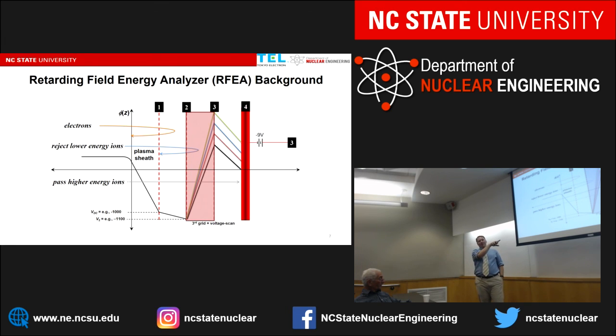The measurement across the resistor on the fourth grid is different, because across the resistor there's going to be a potential drop, so the high part of the potential goes into the high voltage line of the DMM, and the low potential goes into the low voltage line. And as I mentioned, that low voltage line can only sit up to 500 volts above computer ground. So if I scan, taking into account what the VDC is, because the VDC changes where I start and finish my scan, I could only scan between about -500 and 500 volts, because if I go much above that, the computer is going to throw an error because that low voltage line is too high above ground. I wish I could have drawn it, but that's what the main issue was: the potential drop across that resistor is at a high potential all the time.